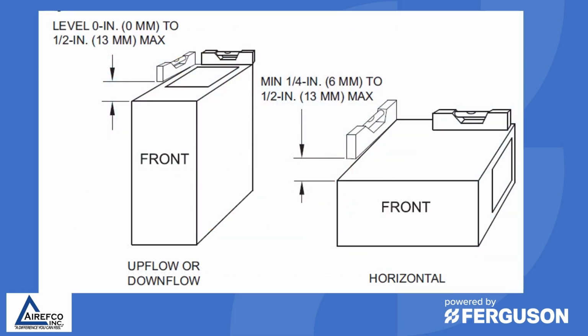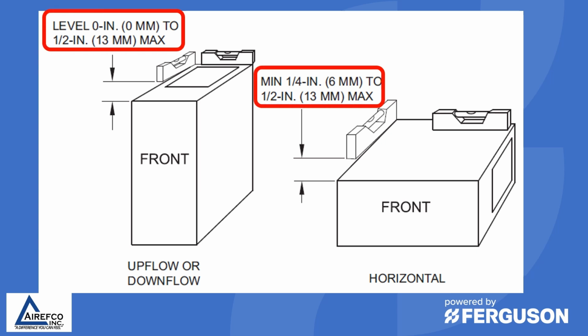Another point in the installation guide that many technicians overlook is to make sure that you level the furnace or slant it towards the front according to manufacturer specifications. In this particular example, on an upflow or downflow installation, you can go level to a 1/2 inch towards the front of the furnace, and on a horizontal application, you can go a minimum of 1/4 inch to a 1/2 inch maximum. If you do not follow these guidelines, condensation can collect at the rear end of the secondary heat exchanger, leading to furnace malfunction and probably secondary heat exchanger premature failure.